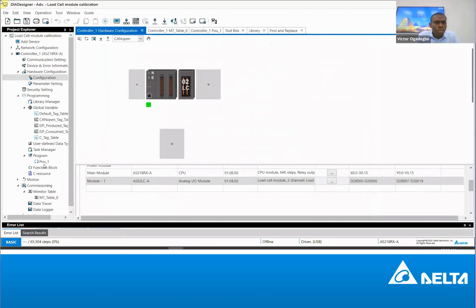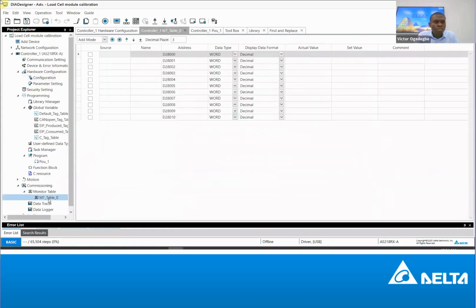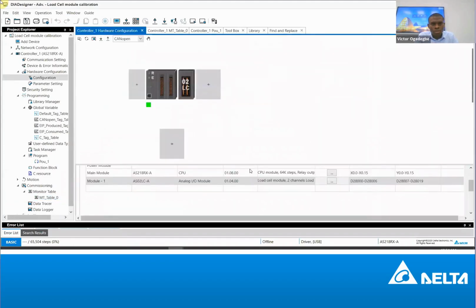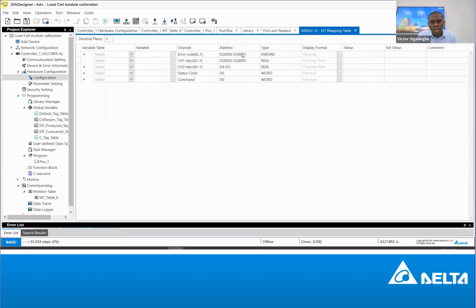Let me also go online. In the program, in the monitor table, I have some monitor addresses. That was the address that was here. If I click on this for the load cell module, you see that this address was automatically assigned by the CPU, the PLC, to the load cell module. So for input channel 1, the value being read is from 28002. It assigned this automatically. What it assigned is so limited, and we have up to about 100 parameters in this module that you can read and write, to and from.